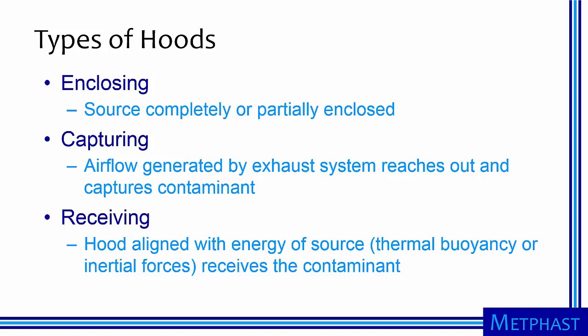I will spend some more time on hoods as they are the point of entry into a local exhaust ventilation system. There is a wide variety of hoods available, with selection depending strongly on the operation being ventilated. We will review hoods in the following three categories: enclosing hoods, which completely or partially enclose the source of the contaminant; capturing hoods, which use the air flow of the exhaust system to reach out and capture the contaminant; and receiving hoods, which are aligned with the energy of the source that helps them receive the contaminant.